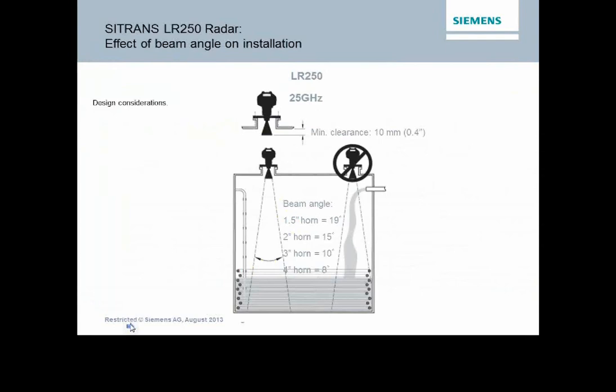And then some of the more common installation criteria would be making sure we're not actually going to see a waterfall or the fill stream when we're doing our measurement. When we get into other radar units, we talk about aiming. The main thing is we're going to be sending out a signal, and we want to optimize the signal that we get back. We're going to take a look at that and actually analyze it. We're going to be able to develop a confidence level in what we see as our material surface to be, and be able to adjust our parameters until we can maximize what that confidence level actually is.